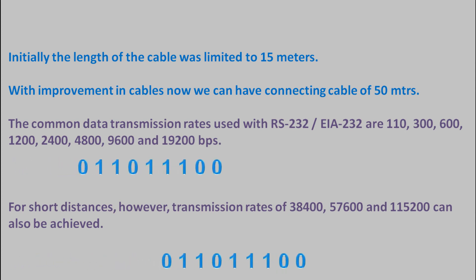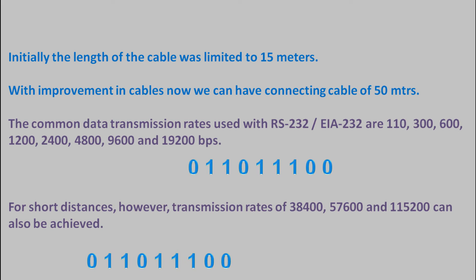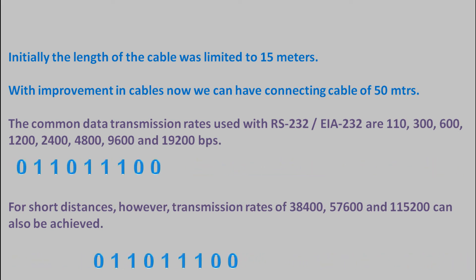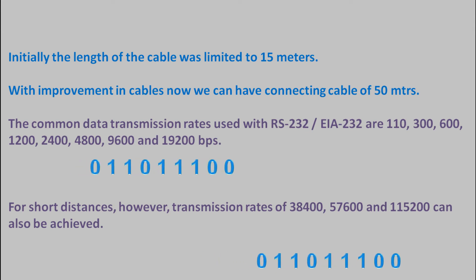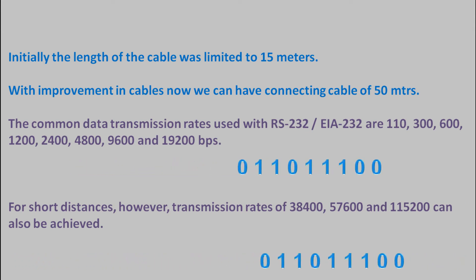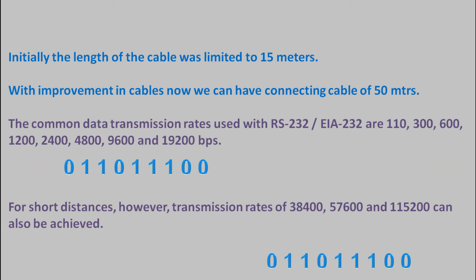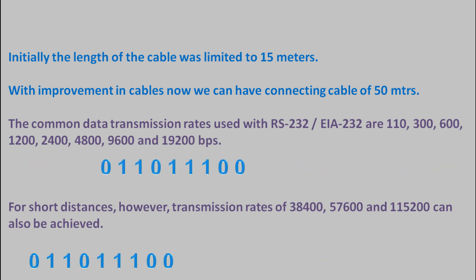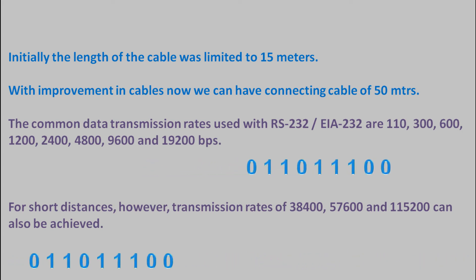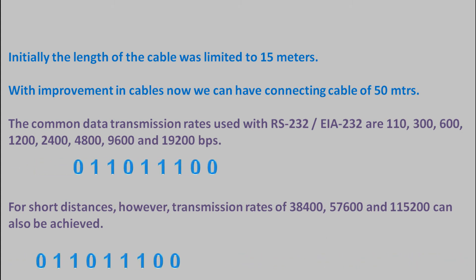Initially, cable length was limited to 15 meters, but with improvements in cables, connecting cables of 50 meters can now be used. The common data transmission rates used with RS-232 are from 110 bps to 19 kbps. However, for short distances, higher data transmission rates up to 115 kbps can also be used.